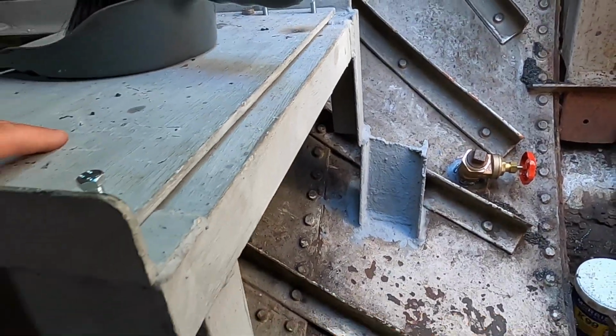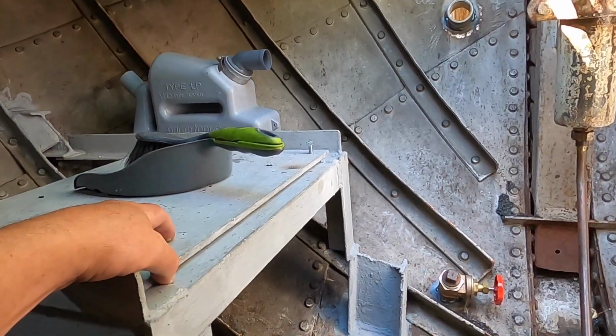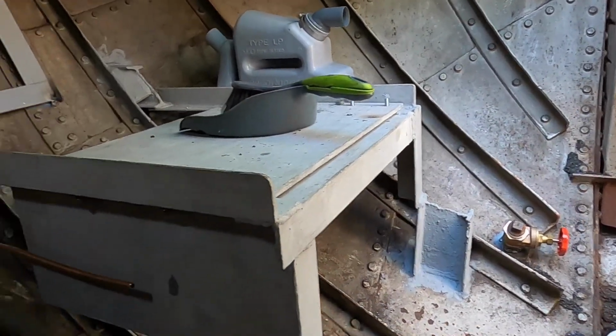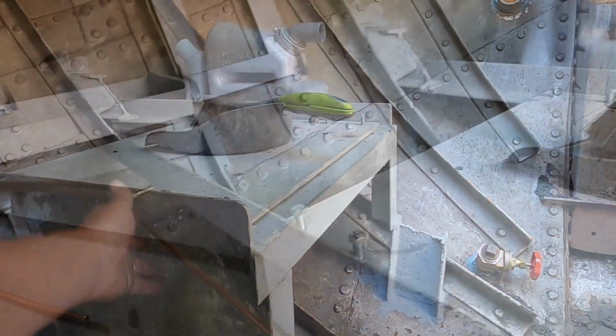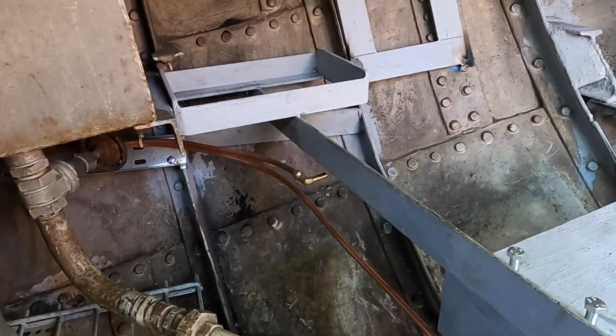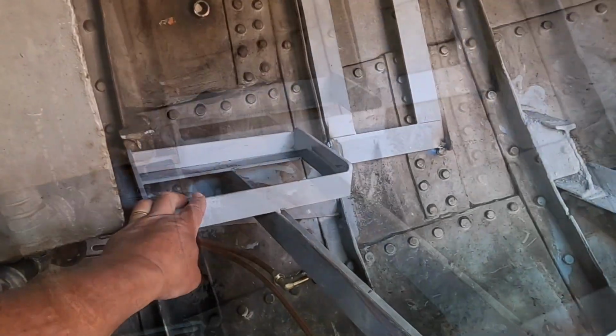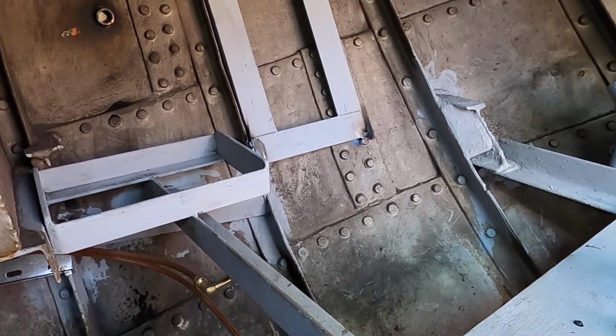This is the stand where the generator is going to sit. It's going to be bolted to this removable plate that will slide out, which will enable us to get the generator out easier. It's going to get run the fuel lines, which are going to go back in and feed off the day tank, so there's a fuel out and return. This is the battery to start the generator. It's going to sit in that box, all nicely made.